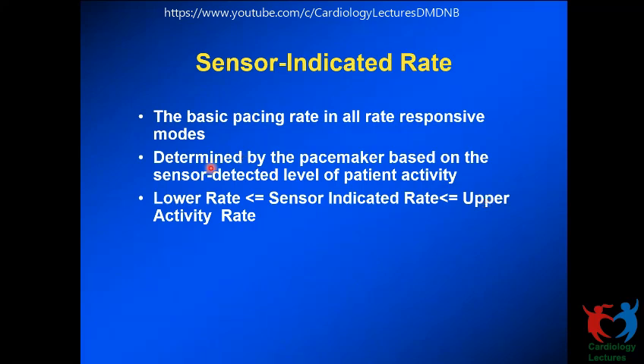And the pacemaker will pace the heart at a rate between these at all times, depending on what the patient's level of activity is. If he is totally at rest, it will be pacing at the lower rate. When the patient is maximally active, it will not pace faster than the upper tracking rate. At all other times, it is in between that, which is the sensor indicated rate.